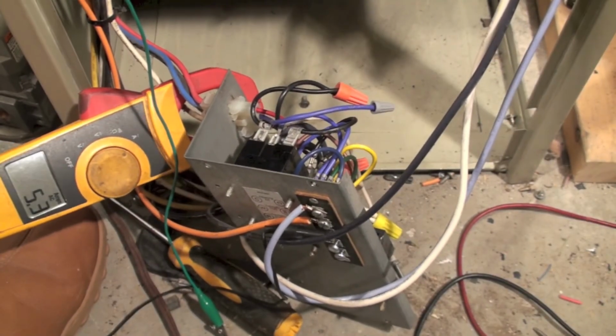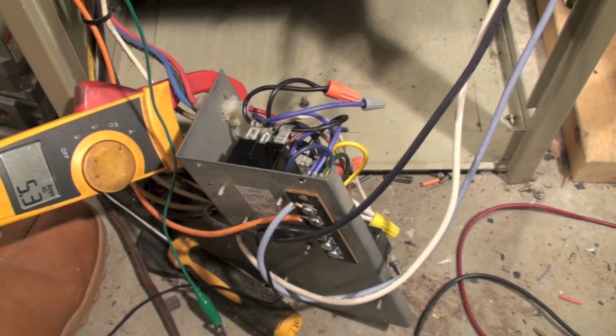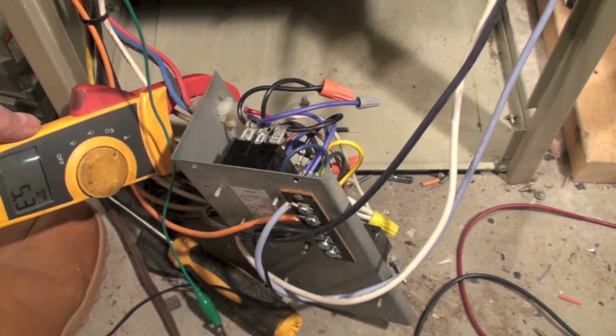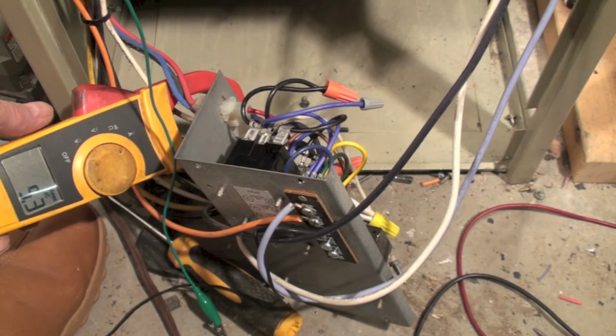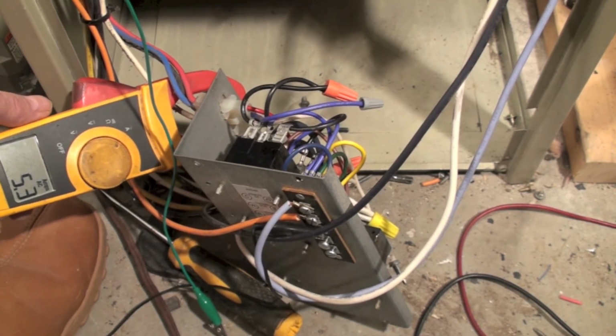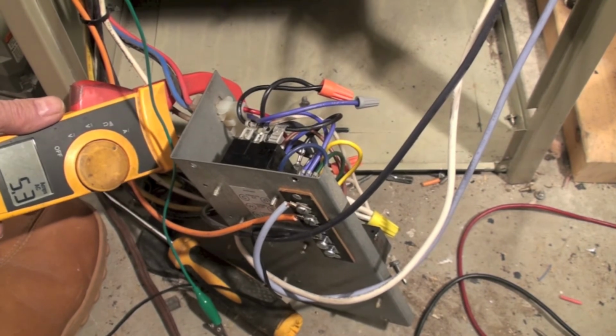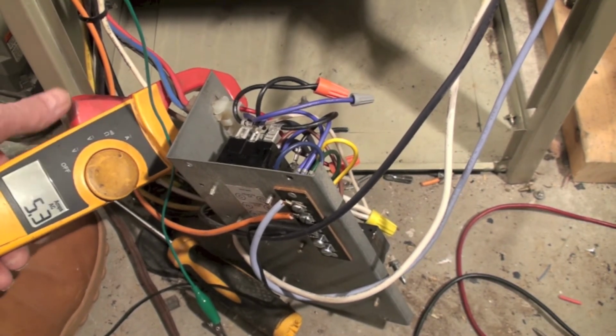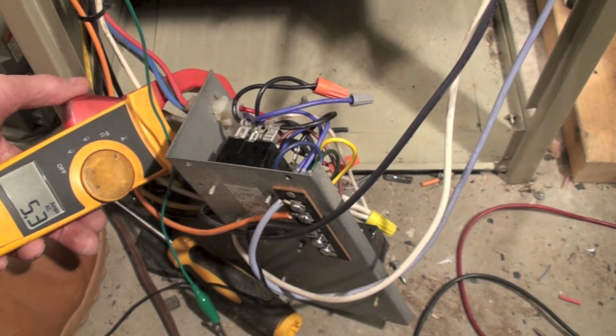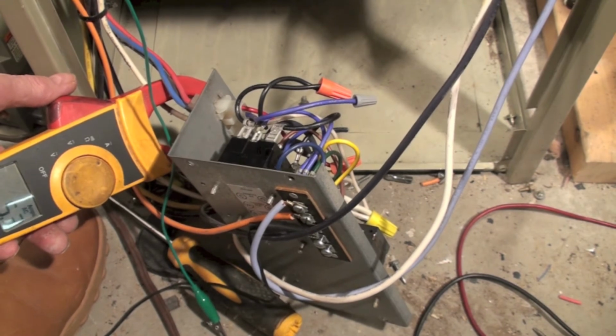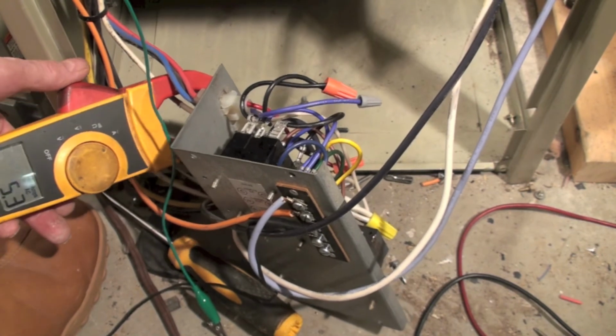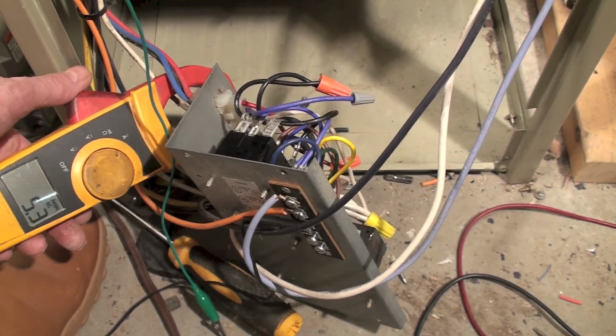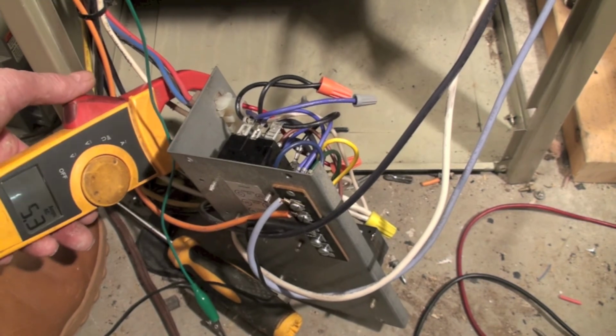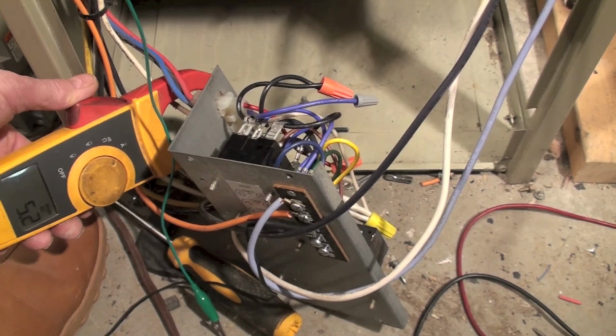Okay, I've got my amp probe put around the common wire, which is white, to the fan, because I got the fan running again to cool this thing down. I'm running 5.3 amps. It's about what it should be. You can't know what the amp draw actually should be on this furnace unless you take the fan motor out and check it out. Sometimes it's a little too much to take the fan motor out. You've got to take the bracket, the belly band off, and all that stuff. And so I oftentimes don't do that. If I'm running in the right area, I'll call it good. And then of course you check the bearings and the like on the fan.